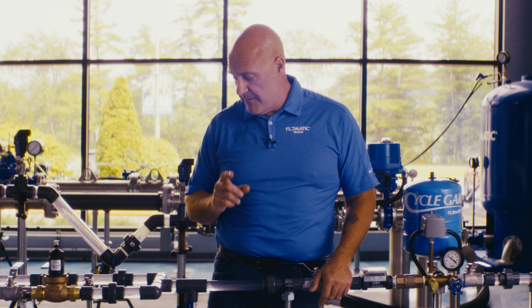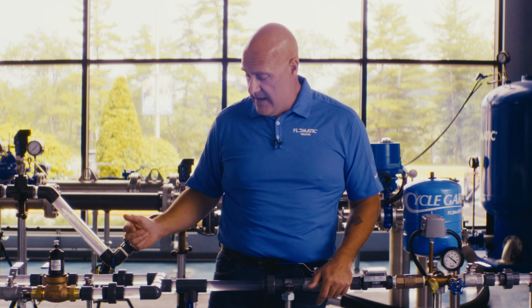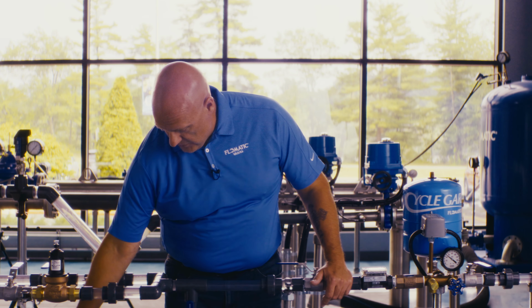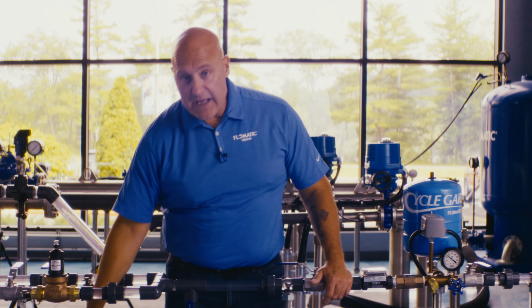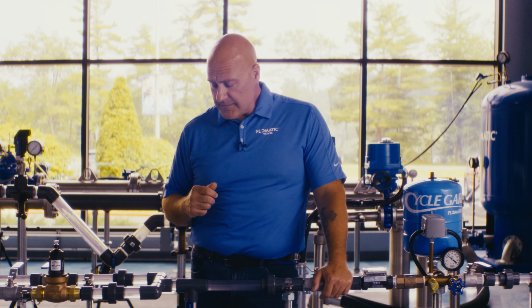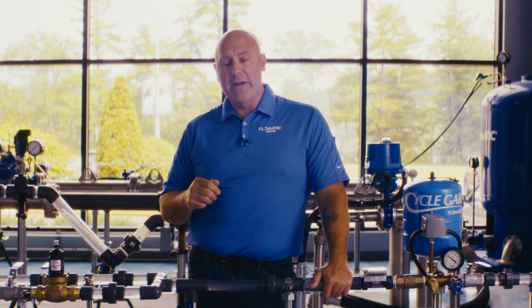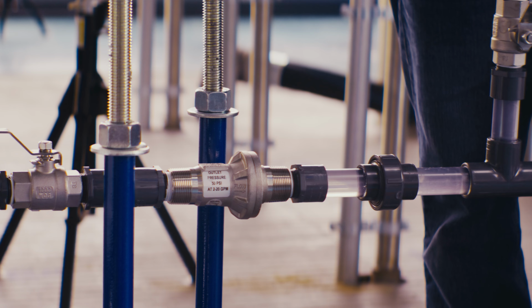It is important to point out with this model that on the underside of the flange, or what would be the pump side of the flange, there is a weep hole machined into the valve body. That weep hole is to prevent the valve from hydrolocking over time. It will not leak constantly, but the potential does exist. That is why we want this valve in the well with the tank. I do not want a C153 located in a basement.